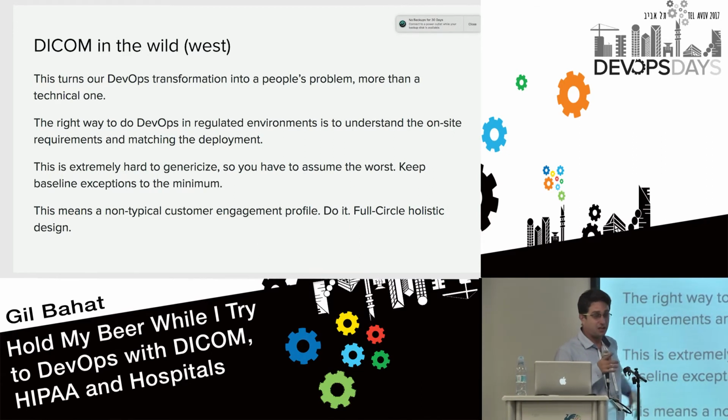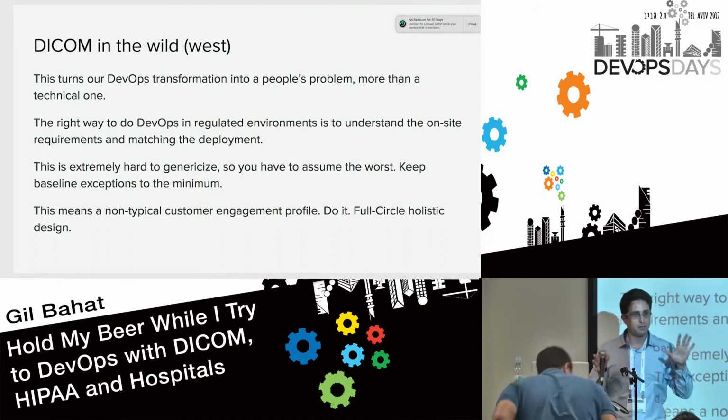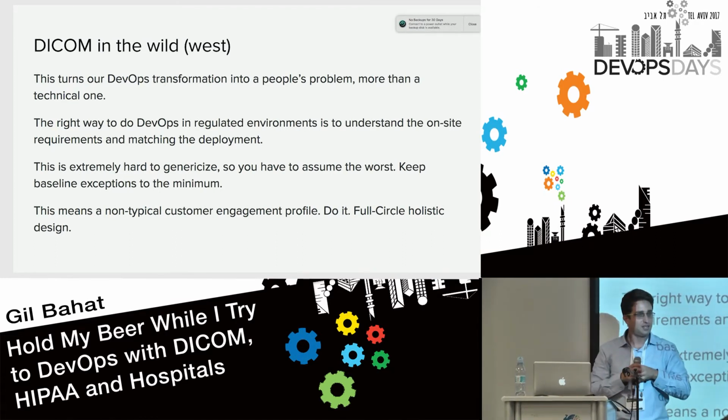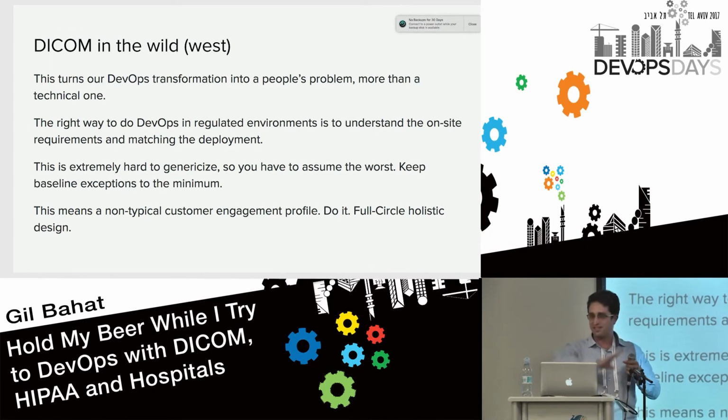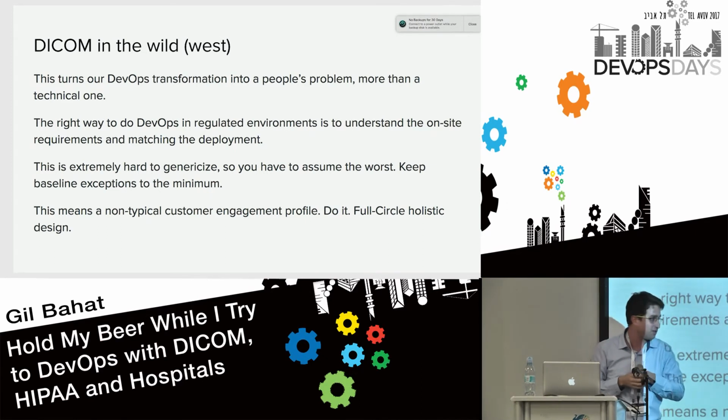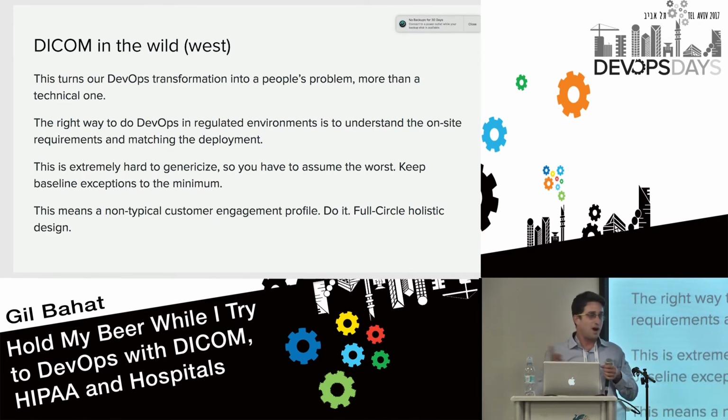Actually, now that we have a few minutes, I'm just going to say something real quick about TLS, because I did actually find in one of the specifications that the modality did support TLS. It was like a discovery of the year. There is TLS support. But it was a specific firmware. So I sent an email to the vendor, saying, hey, why does that firmware have TLS and none of the other firmwares have TLS? And the reply was very nice. They said, thank you for your inquiry. We didn't even realize we had a TLS supporting firmware. This was due to some government agency that insisted on it, and it's never going to see the light of day in any other place.